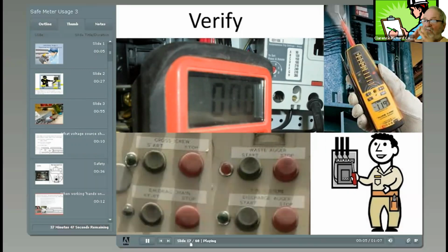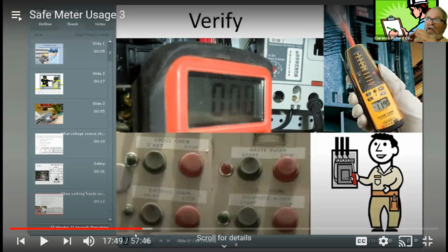OSHA may sometimes require the verification check to be measuring the voltage at the main disconnect, and OSHA may sometimes require the verification check to be only engaging the start button to confirm the machine is inoperable and then returning the switch to the off position before proceeding with servicing. Lockout tagout could be, you could say, once you do your lockout tagout, you can verify, test it, test to see if the thing is going to start up.